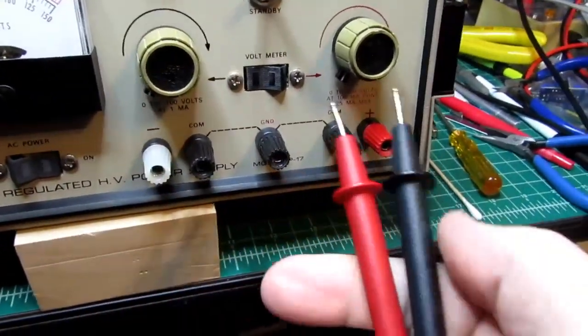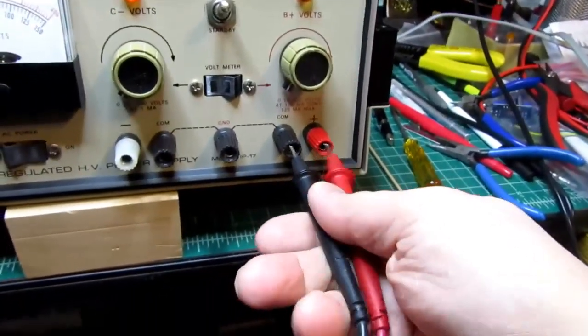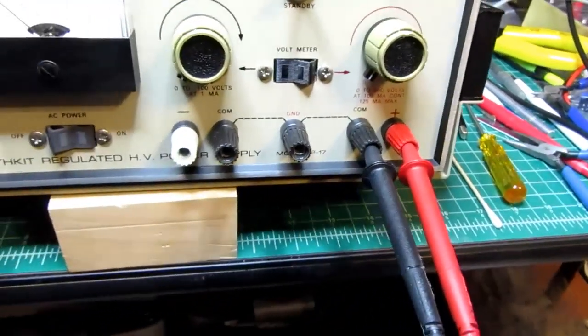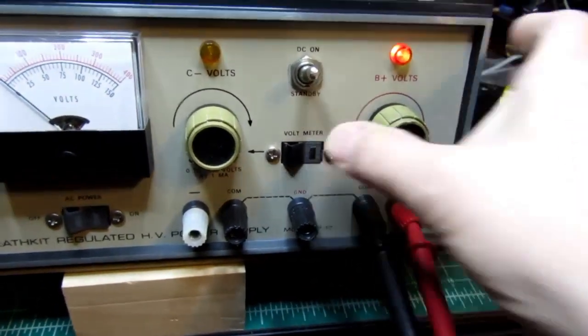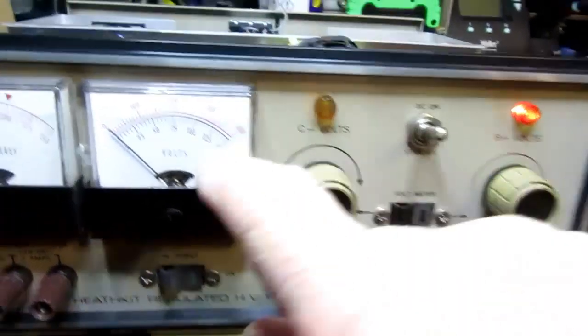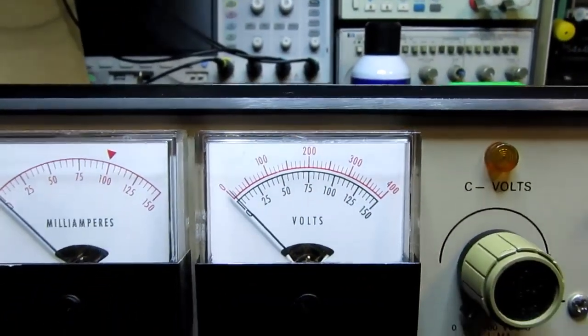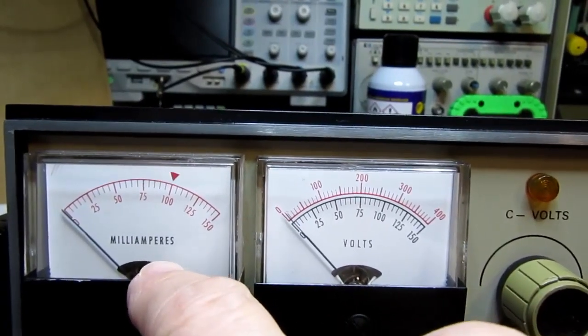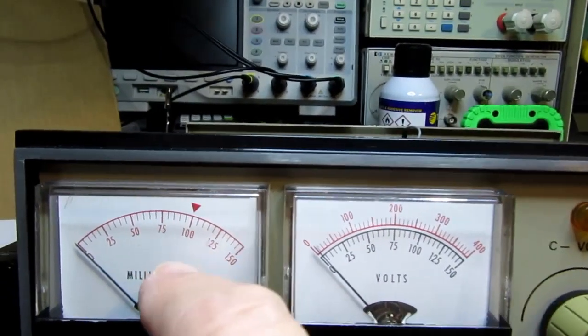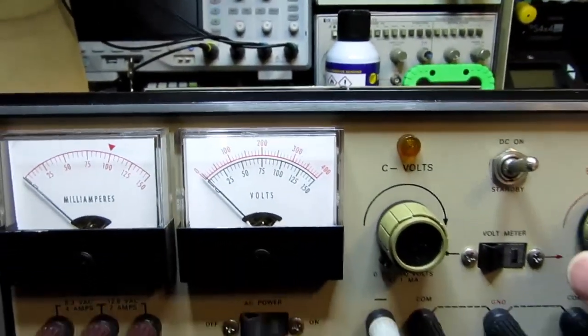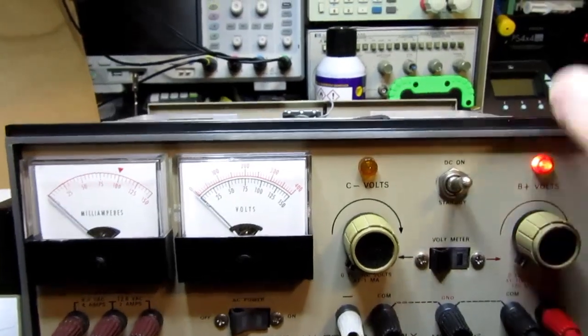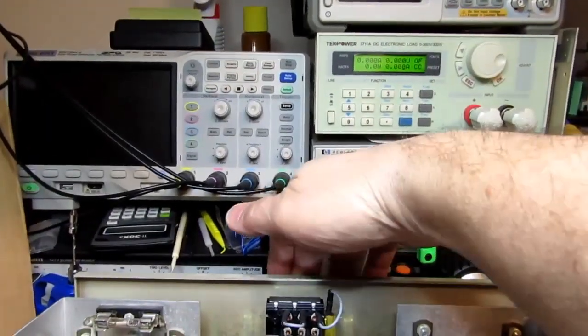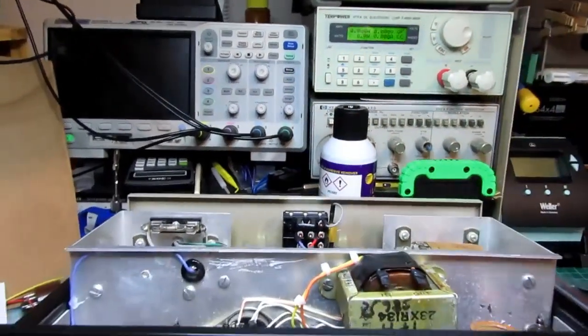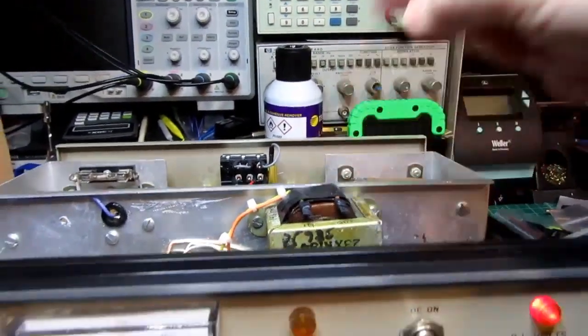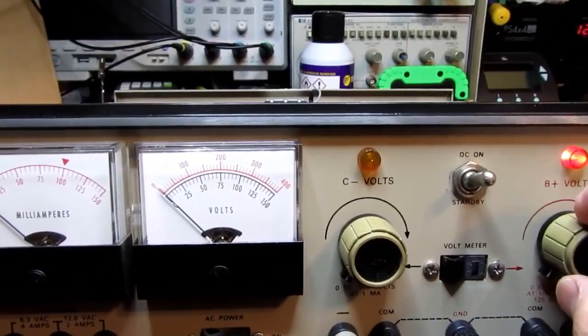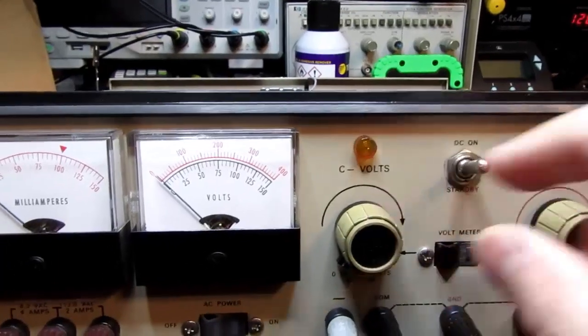Alright, let's go over to this side. I'll switch the meter to the right so the B plus light comes on. Now we'll be looking at the red scale here, and also the milliammeter will now be in effect. Its maximum should be 100 milliamps from that little red arrow. And by the way, I've got the newly added switch in the back put in the normal position, so those extra capacitors and this choke here should not be in the picture. And this pot should be more linear than this pot was.